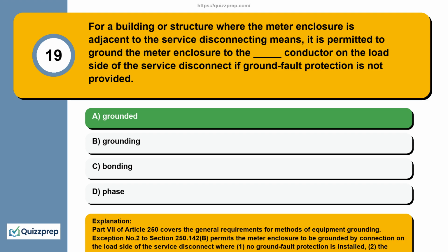Part 7 of Article 250 covers the general requirements for methods of equipment grounding. Exception number 2 to Section 250.142(B) permits the meter enclosure to be grounded by connection on the load side of the service disconnect where: 1. No ground fault protection is installed, 2. The meter enclosure is adjacent to the service disconnecting means, and 3. The grounded service conductor is not smaller than the size specified in Table 250.122.